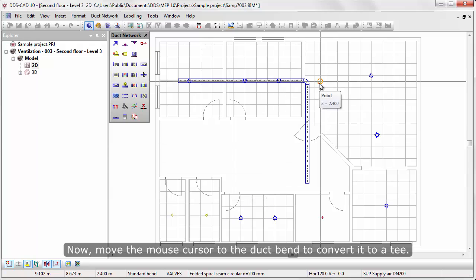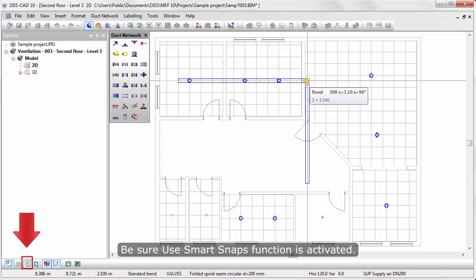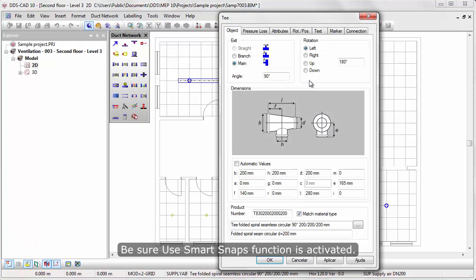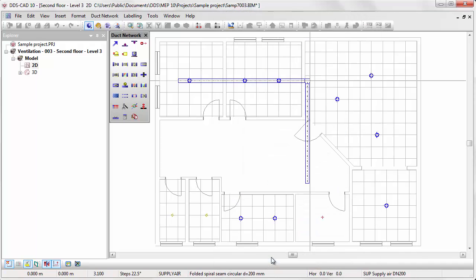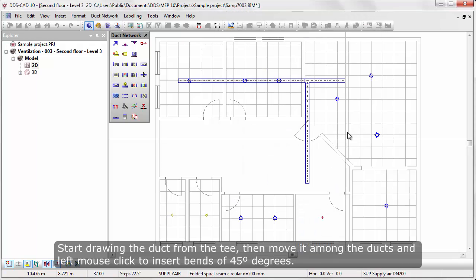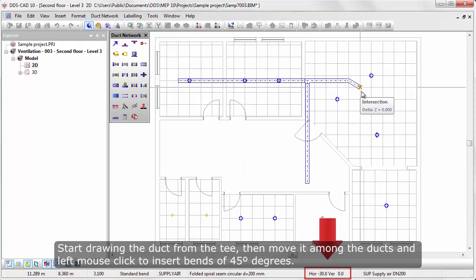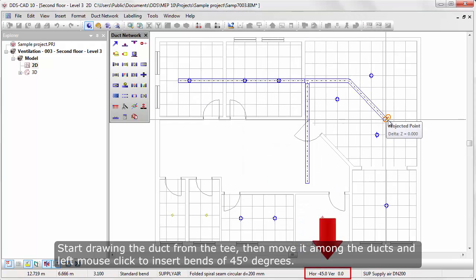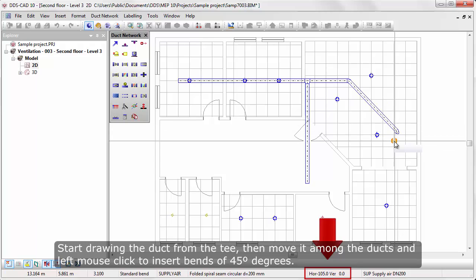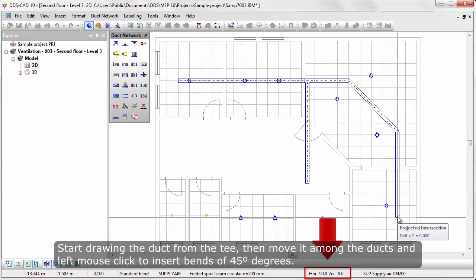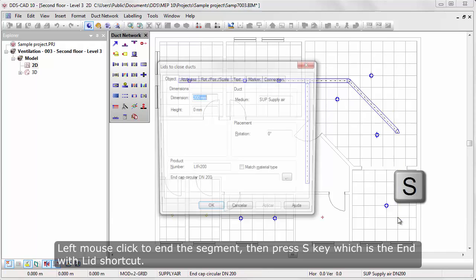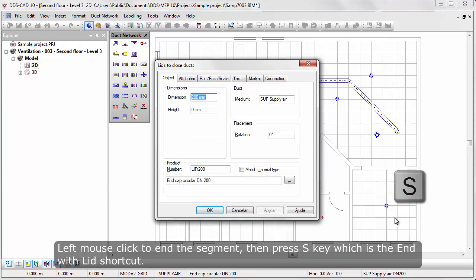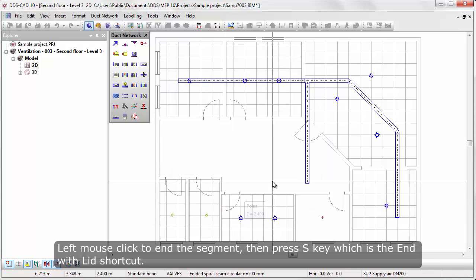Now, move the mouse cursor to the duct bend to convert it to a T. Be sure Use Smart Snaps function is activated. Start drawing the duct from the T, then move among the ducts and left mouse click to insert bends of 45 degrees. Left mouse click to end the segment, then press S key, which is the End with Lid shortcut.